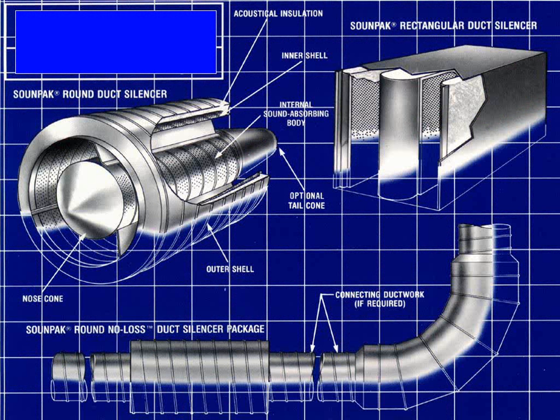Now the converse is round duct. Round duct acts just like your doctor's stethoscope — it conducts sound. We use round pipe rather than square pipe because of a lower coefficient of friction, smoother flow, and less turbulence. Round duct is very stiff and won't let the noise break out; it won't oil-can. So it's good to use if the air handler were in the next room and we wanted to span across without hearing that rumble — I'd like round duct here. But that means it contains all the noise, and there's just more noise going downstream into the next room.